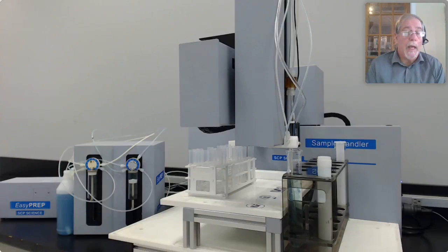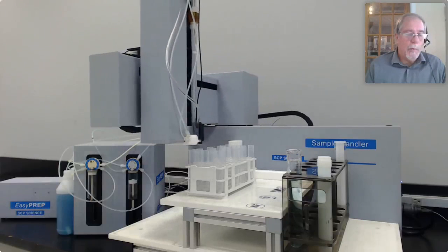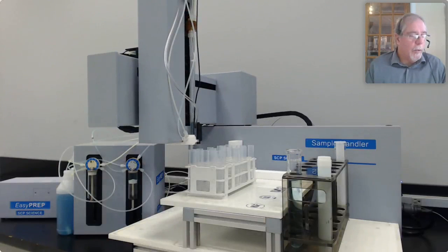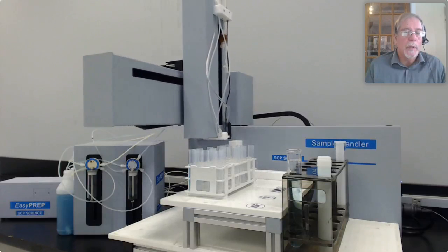And then we will pick up the aliquot and we'll dispense it to an autosampler tube so that you can take it over to your autosampler for analysis. It stays over top of the tube because when we have the bubble stirring, when you turn the bubble stirring off, there is the probability of sample entering that tube. So we turn the air pump on for a split second to ensure that there's no liquid left in that tube.